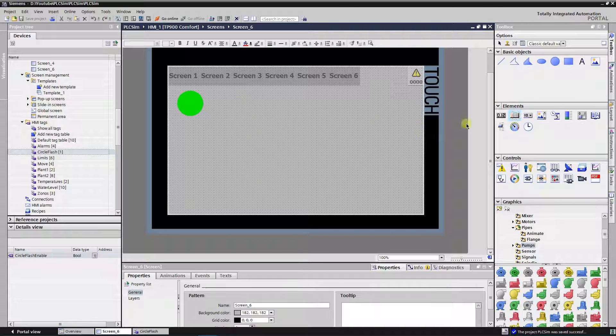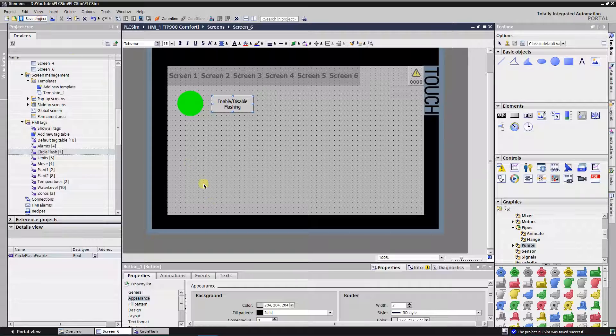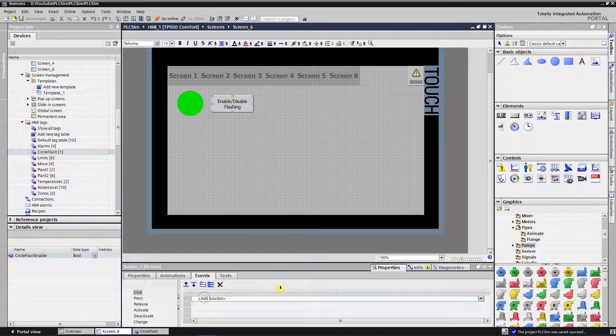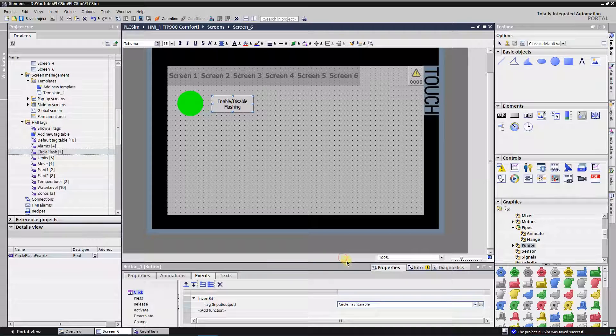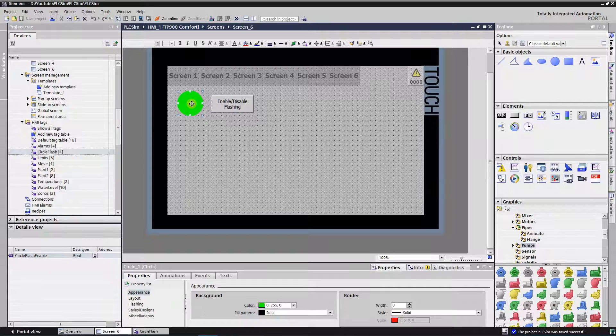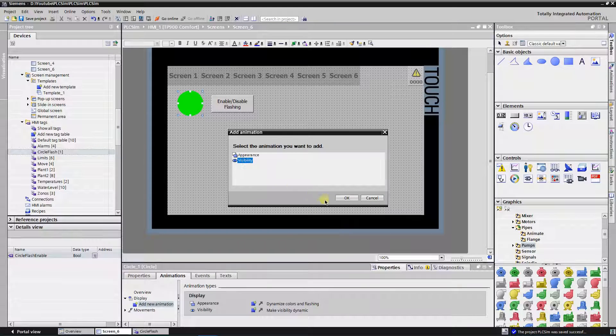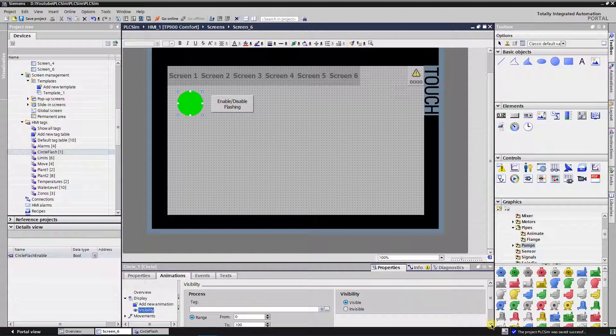Find one in the elements in the toolbox and drag and drop it onto the screen. Write some meaningful text. Switch to the events tab, select the on-click event and find the event called invert bit. Assign the newly created bit. Now select the circle, switch to the animations tab, and double-click on add new animation under display. Select visibility from the dialog window and click OK. Assign the newly created tag as process tag.